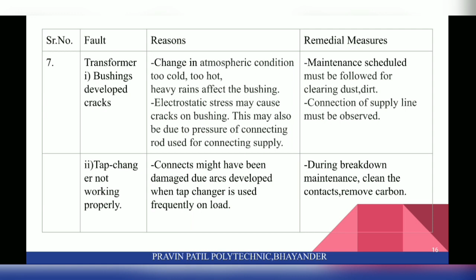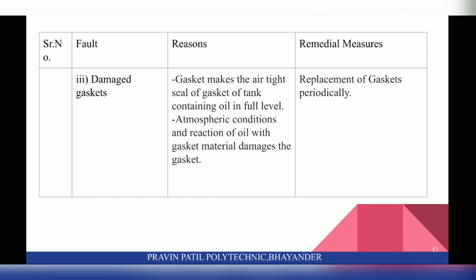Next fault is damaged gasket. Gasket makes the airtight seal of the tank containing oil at full level. Atmospheric conditions and reaction of oil with gasket material damage the gasket. And remedial measure is replacement of gaskets periodically.